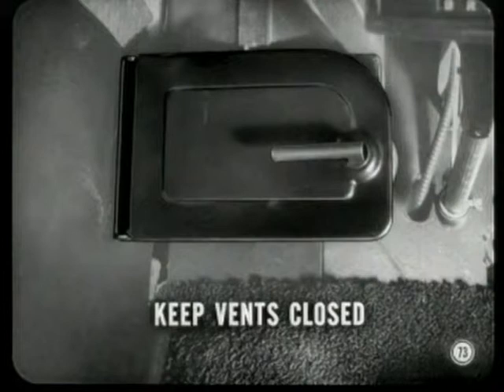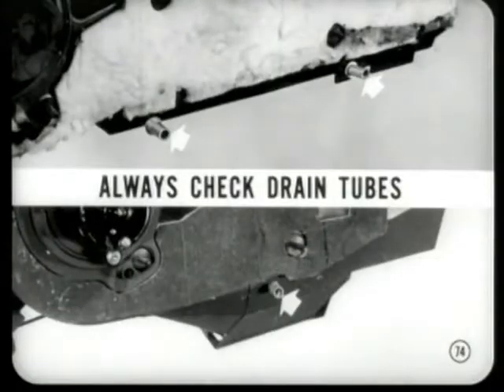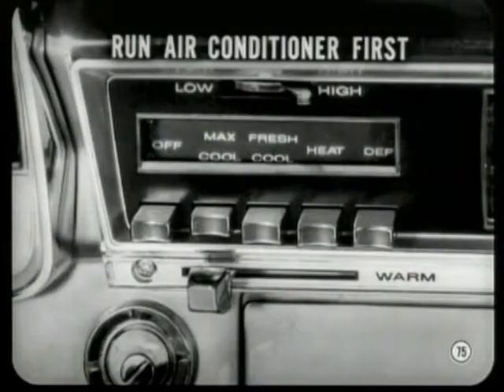Another condensation problem comes from operating the air conditioner with the independent side vents open, especially in humid weather. This one is easy to spot, though, because the customer will usually complain that he isn't getting enough performance from the air conditioner. Of course, the most obvious reason for condensation discharge is an accumulation of water in the drain pan, so make sure the drain tubes are not plugged with dirt or sealer.